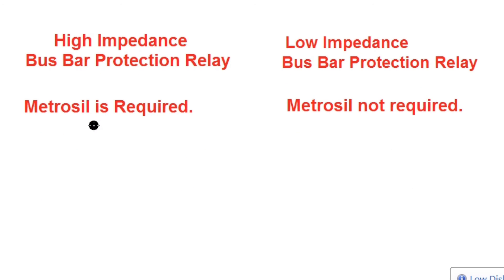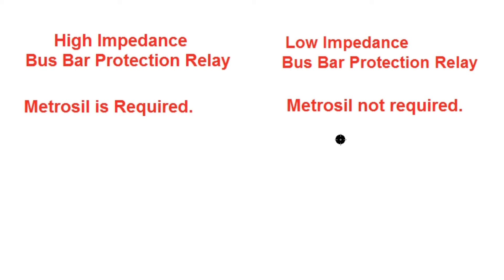Since a high impedance is connected in series with the relay for each phase, during an internal fault condition a high voltage spike may occur, which may damage the relay insulation. Therefore, a Metrosil (surge protection device) is required, connected in parallel with the resistance and relay combination — one Metrosil per phase for high impedance bus bar protection relay. In case of low impedance bus bar protection relay, no such Metrosil is required.